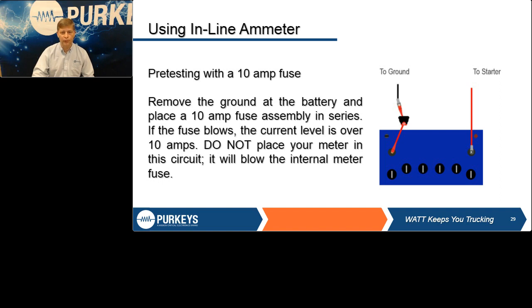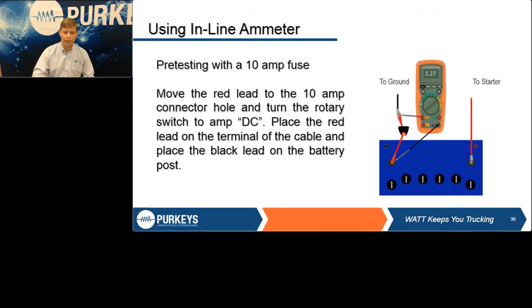Once we put this fuse holder in and it doesn't blow, we take our meter, make sure it's set up properly with the knob in the right function, and the leads in the right position. The ground, bottom right on most meters, stays in that position, but your red lead will have to move. The meter we're showing has a 10 amp port and a 200 milliamp port, so make sure you're on the right one.